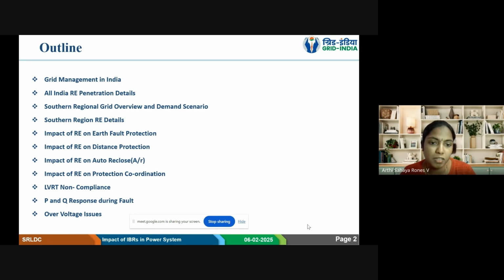Some of the things that we are going to cover in today's session will be the impact of RE on earthfault protection, distance protection, auto reclose, protection coordination related issues, LVRT non-compliances, the reactive and active power responses during the fault, and finally some overvoltage issues in RE pockets. I hope the session will be interesting because all of these are based on real cases, what we have observed in the grid during day-to-day operations.